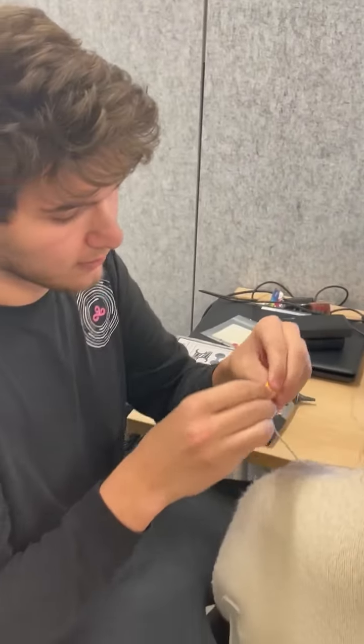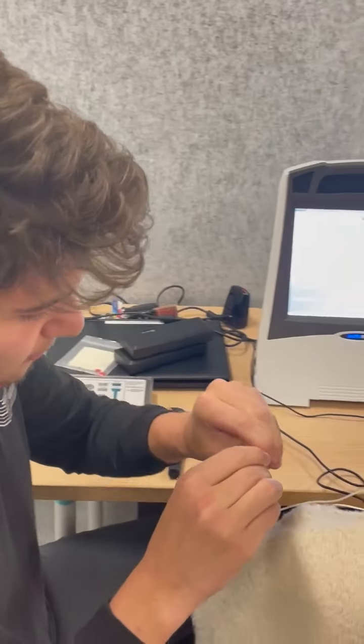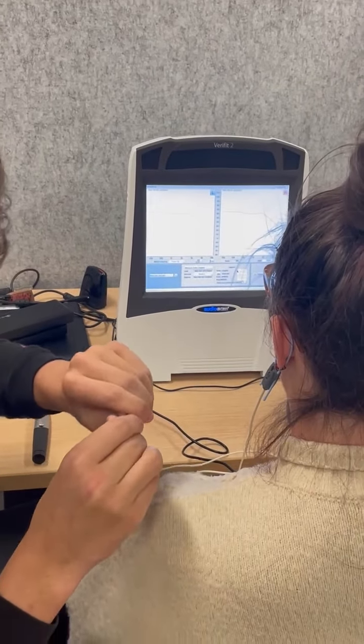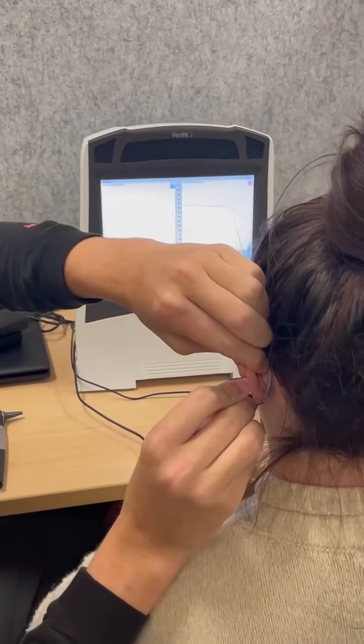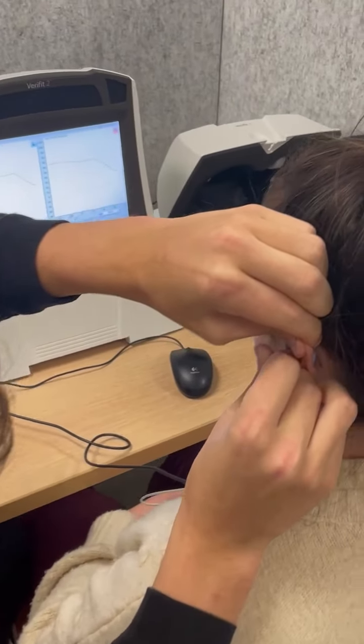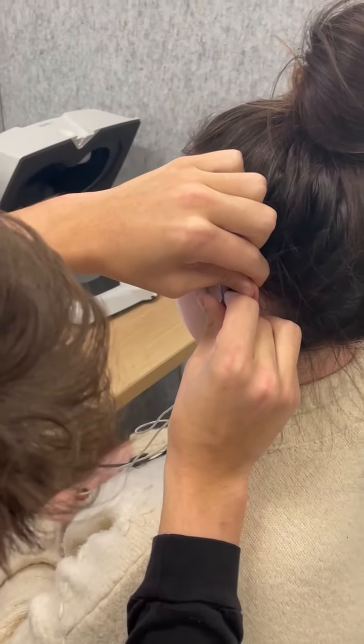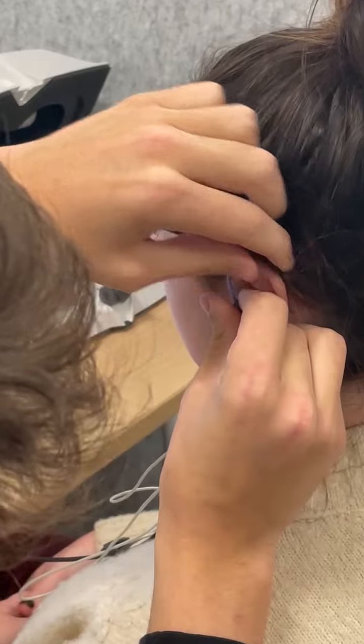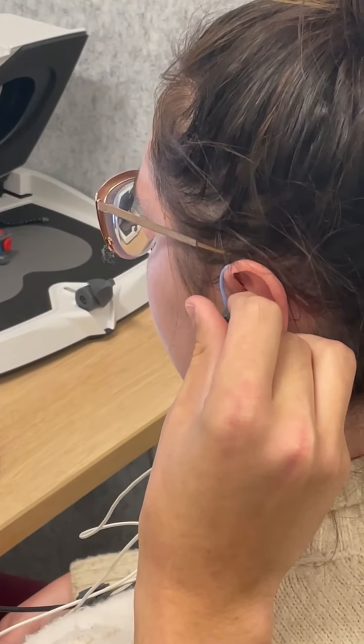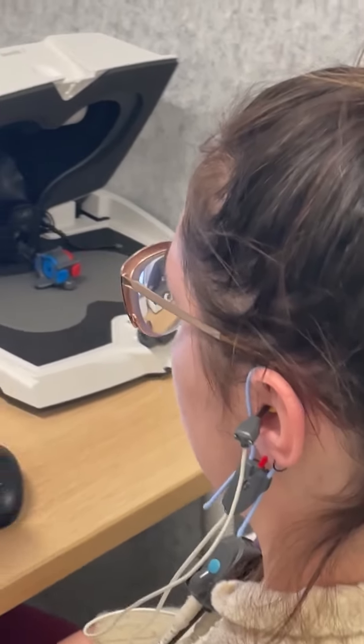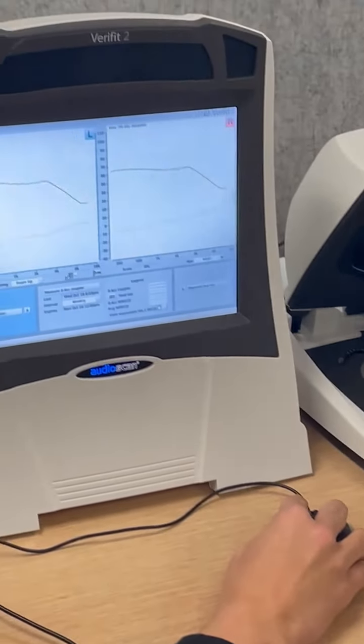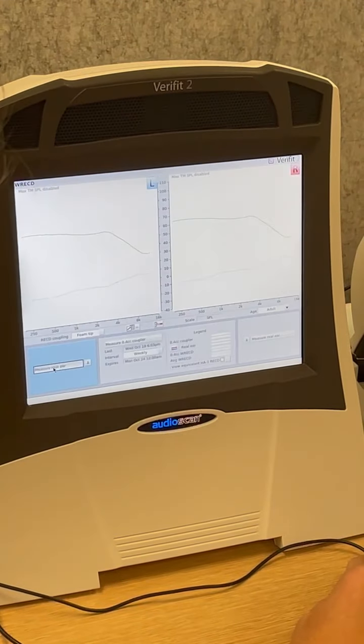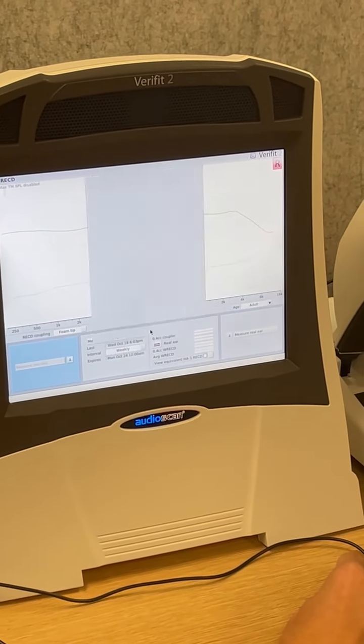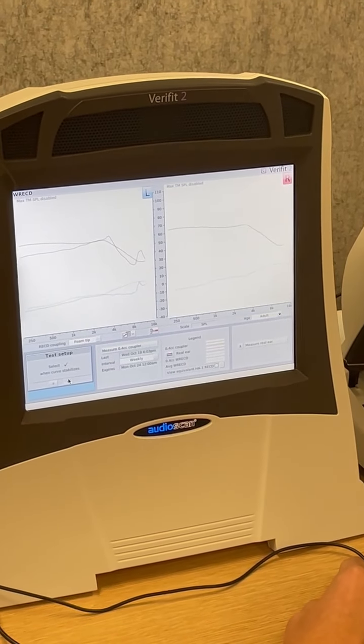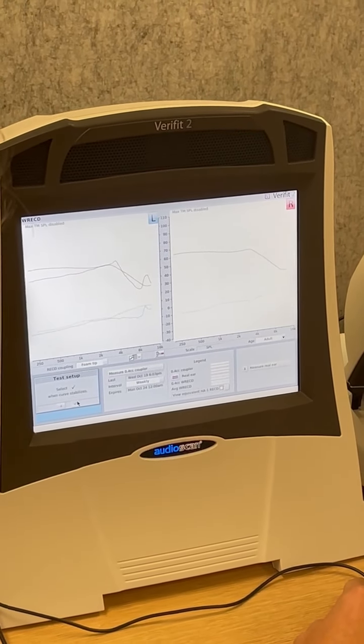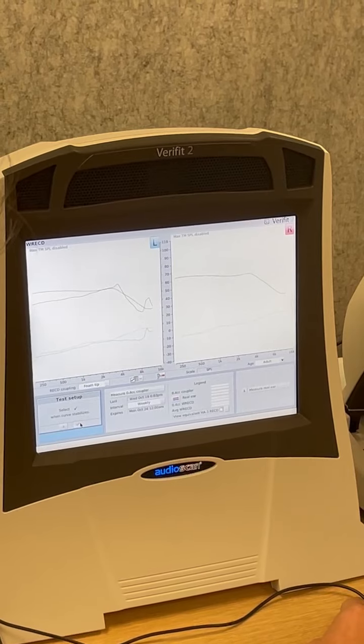And after we complete that, now we can finally squish up that insert and put it into the patient's ear, where you can hold it for a second if you'd like, as I do here, just while it expands. We then head over to the Verifit screen once again, where we can right click and head to the WRECD tab and then hit measure real ear, followed by pressing the check mark, and then we wait for that curve to stabilize before pressing that green check mark once again.